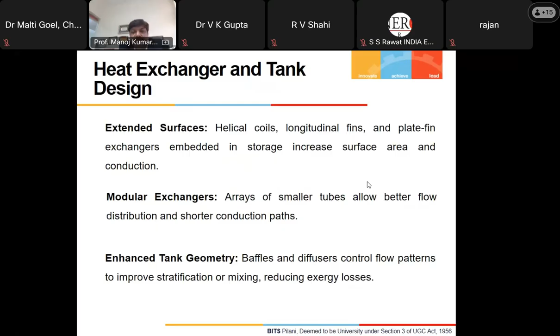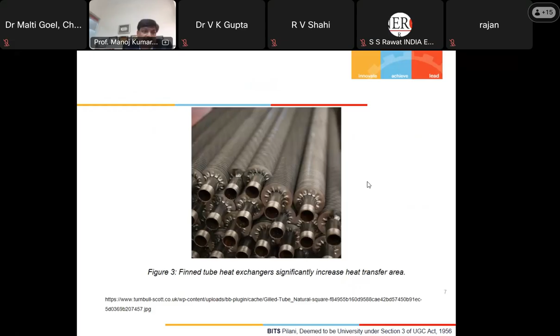Tank geometry can be enhanced by adding baffles and diffusers to control the flow pattern, so that stratification occurs, with high temperature fluid at the higher level and low temperature fluid at the lower level. Where we want stratification or where we want mixing, the system has to be modified accordingly, so we can minimize exergy destruction or losses.